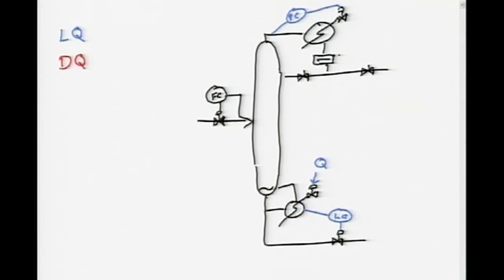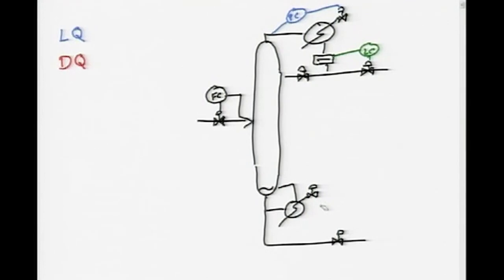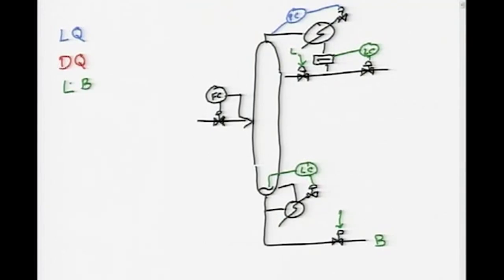We may also have a situation where level control on the top is the usual way. In the bottom, because the bottom stream is a trickle, level cannot be effectively controlled using that trickle. Therefore, the level in the bottoms has to be controlled using the reboiler duty. That leaves the bottom stream, and the operator has to set L and B in order to get the desired separation. That structure is called LB.